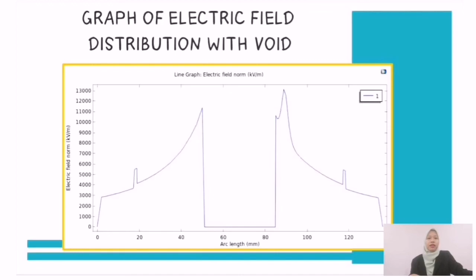So, for the conclusion, the characteristic of electric field includes having void and without void. According to the modeling result, the electric field inside the cable will be distorted compared to the usual operating state, and the insulation between conductors will probably break down. Second, accurate estimation of electric field distribution inside both a perfect and a flawed cable was achieved using a very dense mesh of boundary elements. In the case of a defected cable, the electric field strength is significantly increased inside the void defect. The variation of the electric field value inside a typical high voltage cable agrees very well with theoretical results obtained using simplifying assumptions.